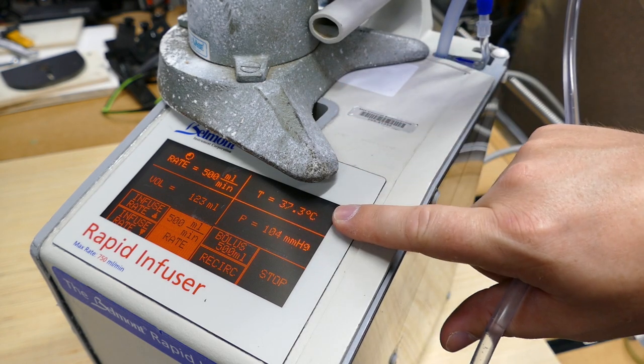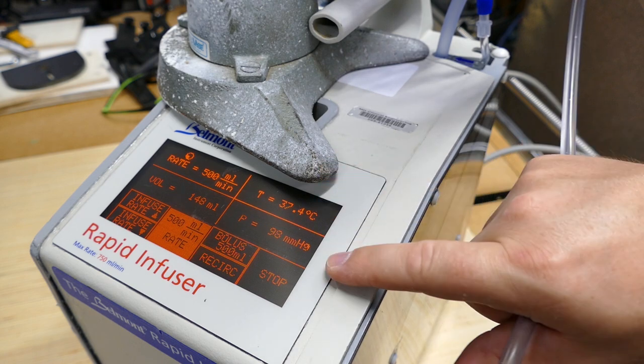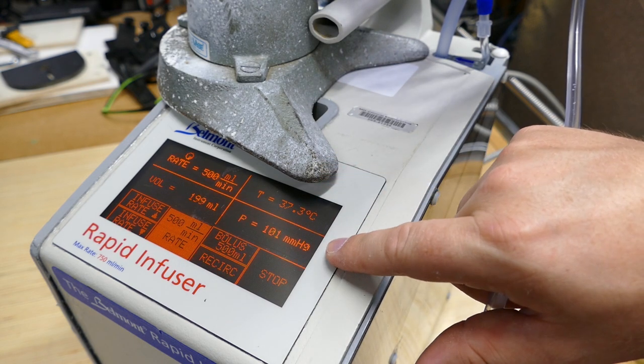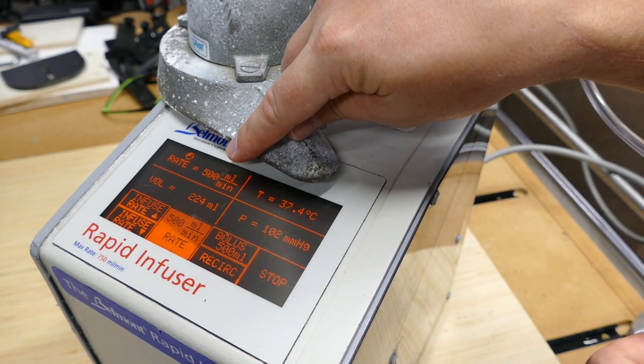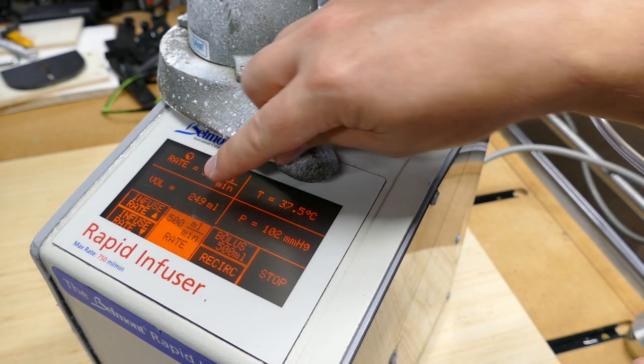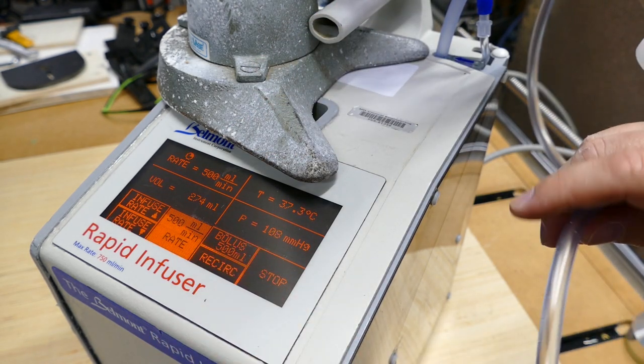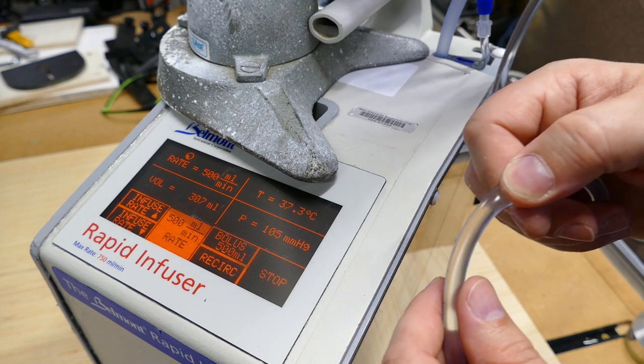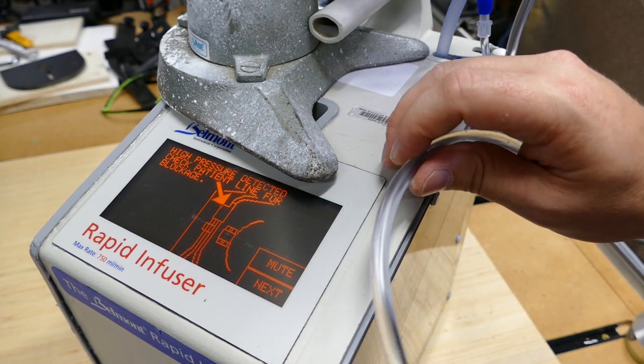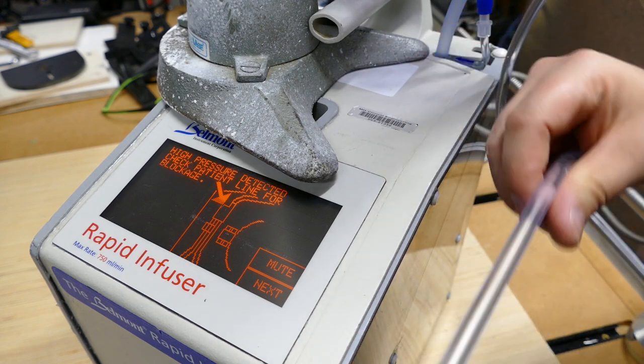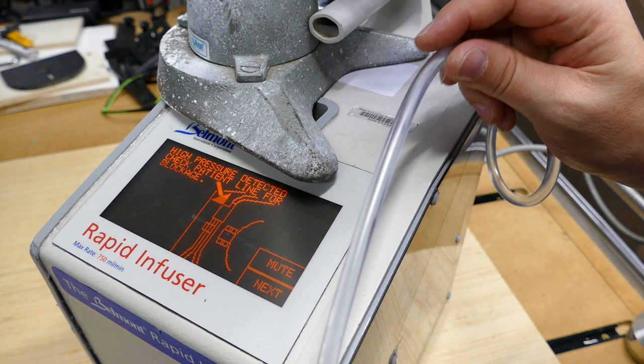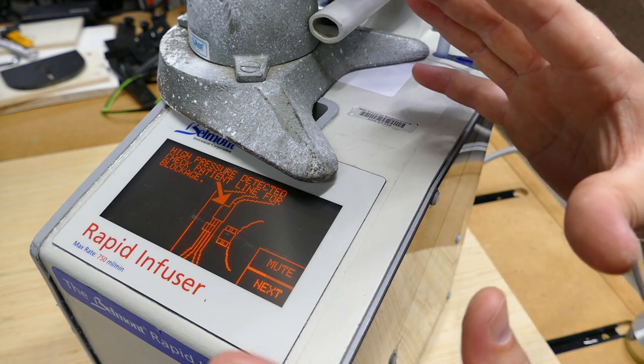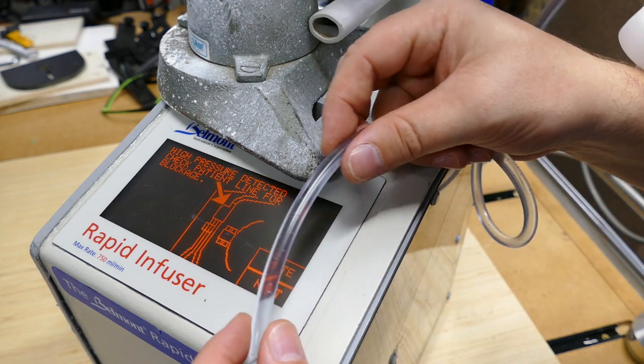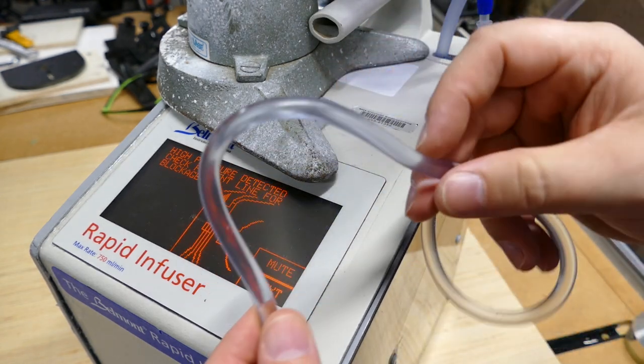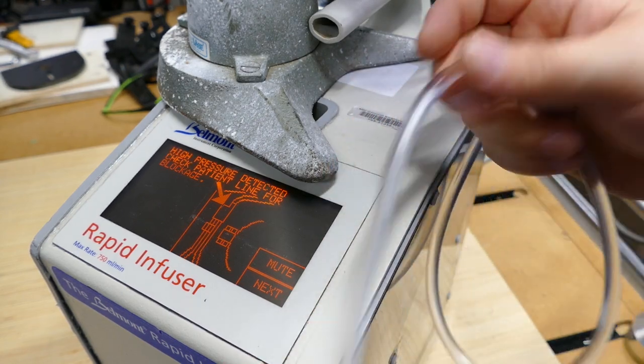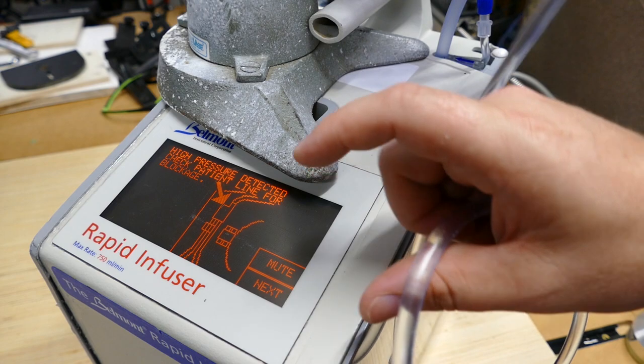It gives us our current temperature, which is 37.8 degrees C, and our current pressure, which is 100 millimeters of mercury. Our flow rate, 500 milliliters per minute, and our current output volume. You can set it up for a bolus if you want, but there's no need for that for us. If you pinch the patient line, it senses an occlusion. That is one of the highlights of this machine, is if you have an occlusion on the patient side, it's not going to blow out the patient's vein. The unit will sense that there's increased pressure. It will stop it. You're supposed to either undo the line or make sure that your patient is stuck good enough with the needle, and then you can proceed.